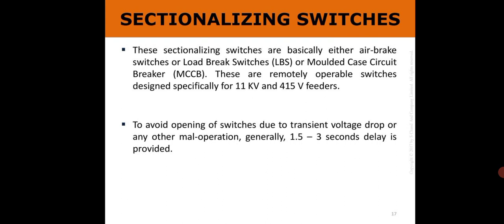We have to discuss the sectionalizing switches. In this, the sectionalizing switches are basically either air break switches, load break switches, or molded case circuit breakers, means MCCB. These are remotely operable switches designed specifically for 11 kV and 415 V feeders to avoid tripping of switches due to transient voltage drop or any other maloperation. Generally a 1.5 to 3 seconds delay is provided.